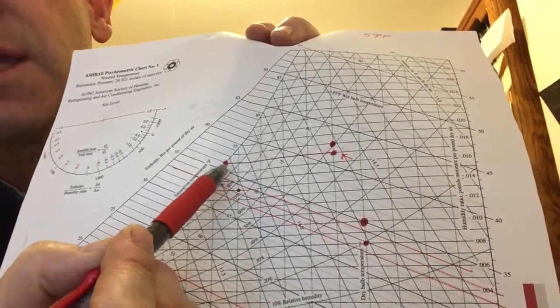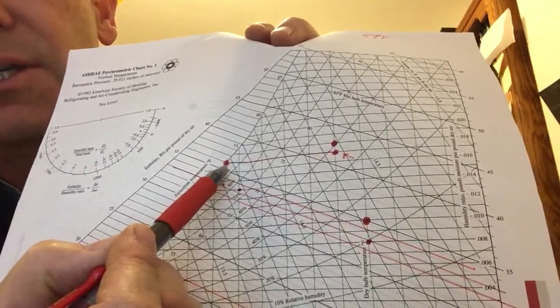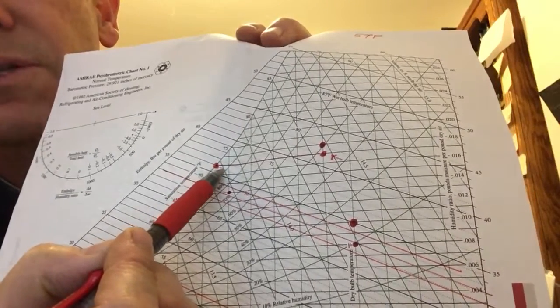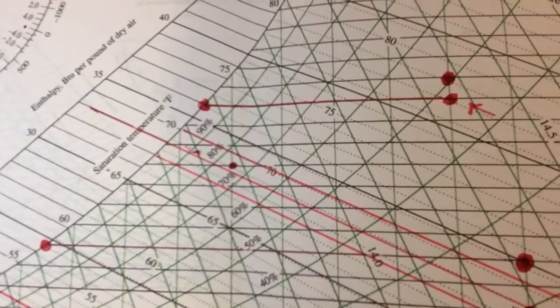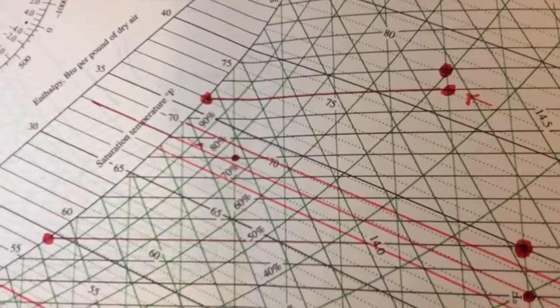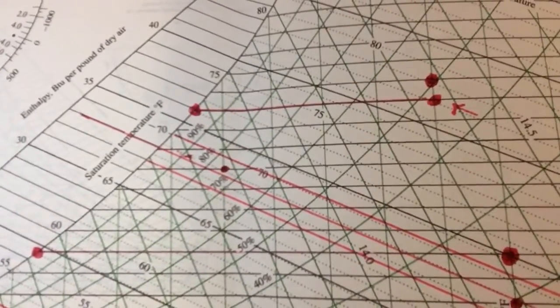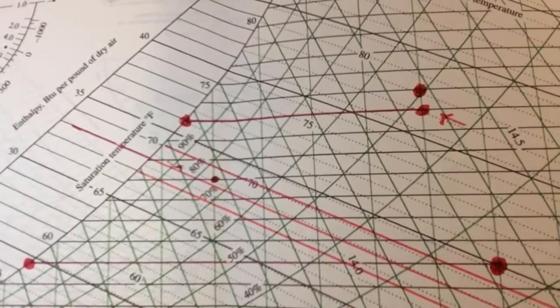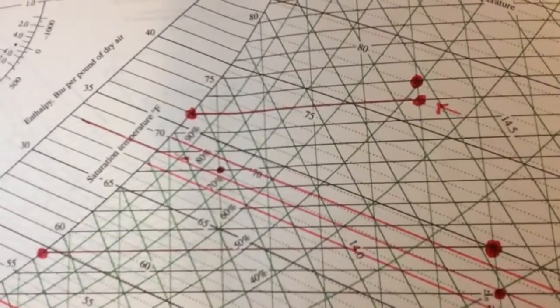When it reached this point, we would start to get condensation, and so we want to be more precise on what that is. So once again, we look at those dotted lines coming off there, and we can see the 70, the 71 line. 72 looks right about where my dot is. 73, 74, 75. I think if you called it 72, that would be good enough, but it looks like it's slightly over. 72.1 degrees is my second one. Okay, so the dew point is 72.1.